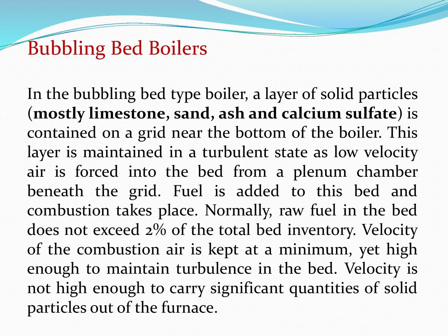Normally, raw fuel in the bed does not exceed 2% of the total bed inventory. The velocity of the combustion air is kept at a minimum, yet high enough to maintain turbulence in the bed. Velocity is not high enough to carry significant quantities of solid particles out of the furnace.